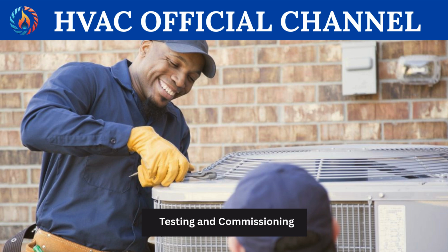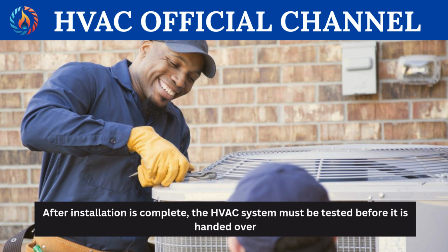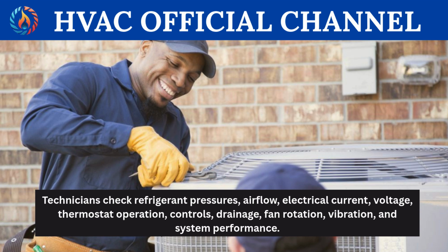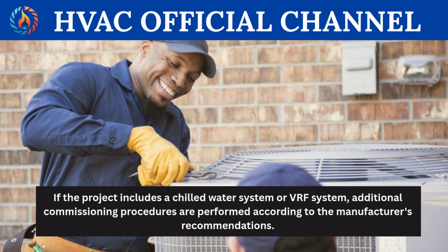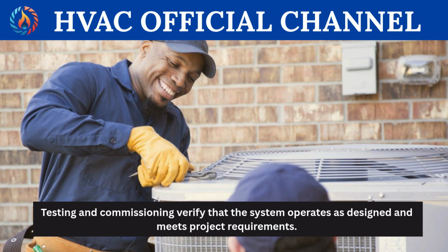Testing and commissioning. After installation is complete, the HVAC system must be tested before it is handed over. Technicians check refrigerant pressures, airflow, electrical current, voltage, thermostat operation, controls, drainage, fan rotation, vibration, and system performance. If the project includes a chilled water system or VRF system, additional commissioning procedures are performed according to the manufacturer's recommendations. Testing and commissioning verify that the system operates as designed and meets project requirements.